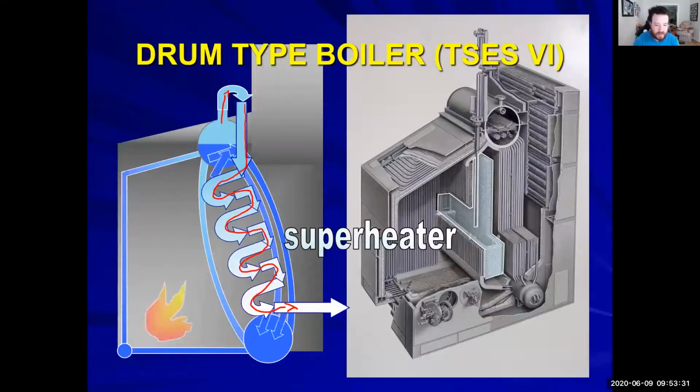And that's what our superheater is about. We are increasing the temperature of our gas, of our steam. So there is no liquid present, and if there is, it's all gone at this point. So we are increasing the temperature, and we're going to be exiting as a high pressure, high temperature gas. 600-pound steam at like 800 degrees.